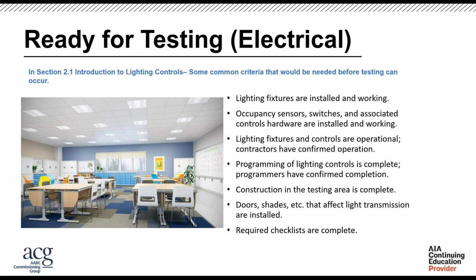A lot of times, testing becomes very cumbersome, for example if you're trying to test vacancy or occupancy and there are people moving throughout the space doing other construction work. These are some of the biggest things we run into, where we say, hey, are you really ready for testing? Your doors, shades, everything you're going to need to test the lighting needs to be installed and ready. A lot of times shades are some of the last things to come on board, especially if there's a specific shades manufacturer or controller. These things should be ready before we go out and test, to avoid retests or delays. A lot of times these are on our checklist to make sure they're completed. If those are completed, most of the time these other steps are in place.